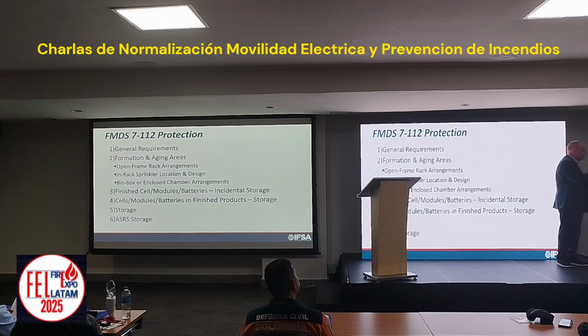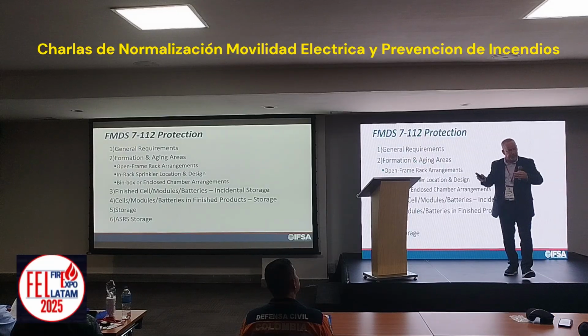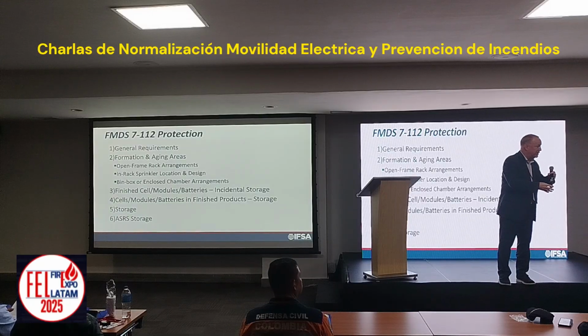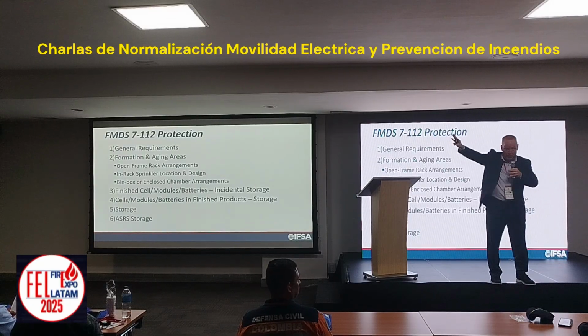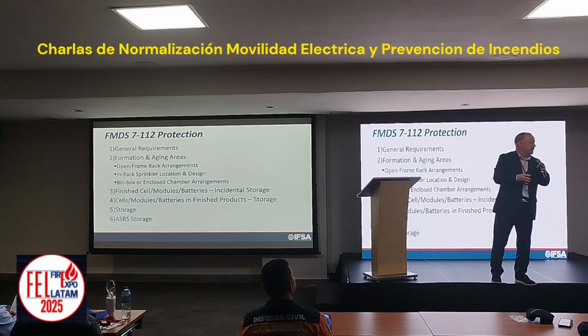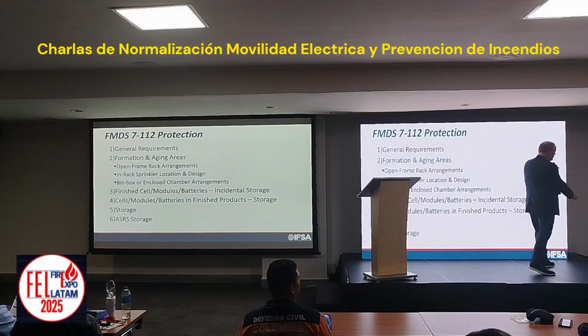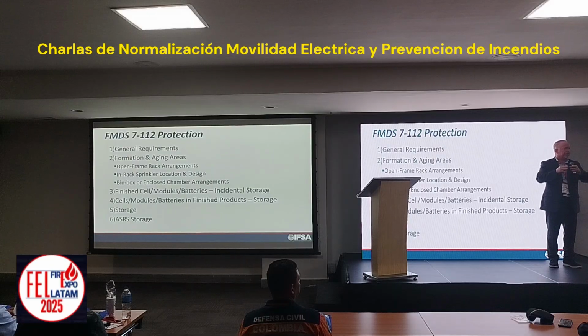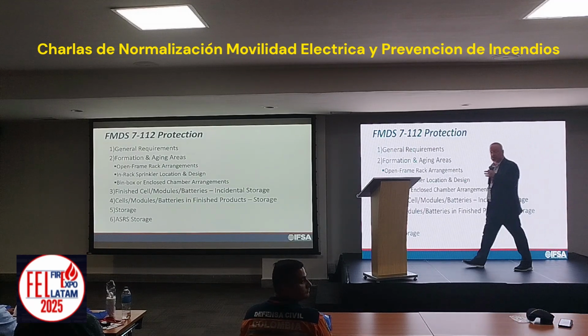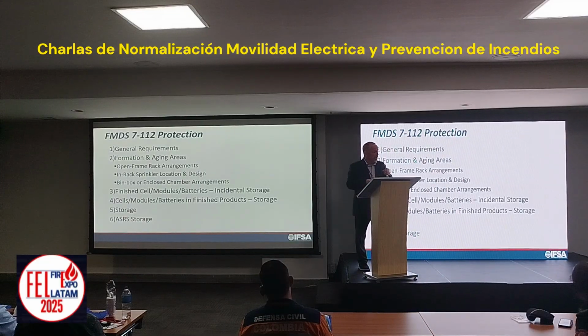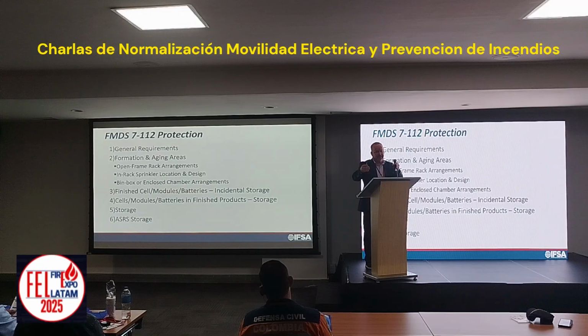Item 5 then becomes the storage of the batteries. What if they come out manufactured and they're not in incidental storage or in the final product? They're simply being stored as batteries to be shipped off to somebody else - that's a different design criteria. All of these things, including ASRS storage - automated retrieval systems, another challenge altogether for sprinkler systems - all of these design parameters and design guidance is provided to you in 7-112. That gets us through the process, providing the sprinkler designer guidance as to how much water is needed and what density of design is required.